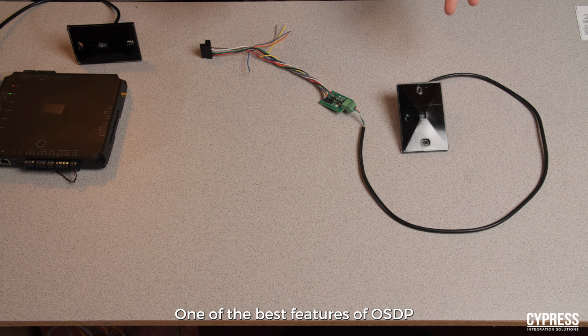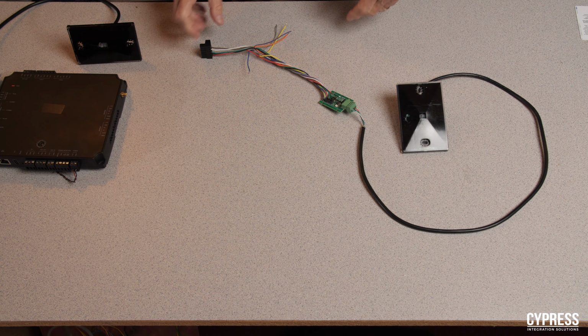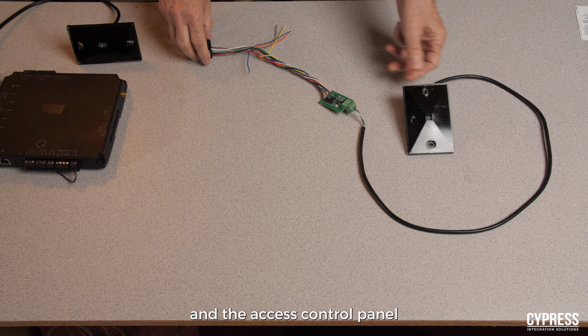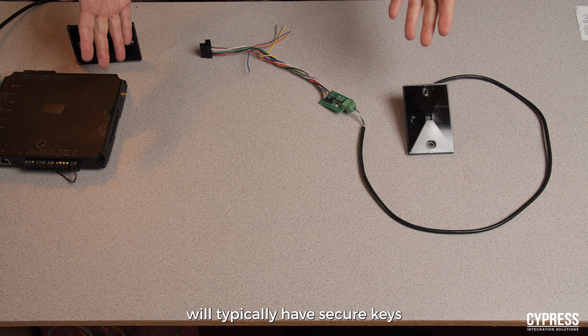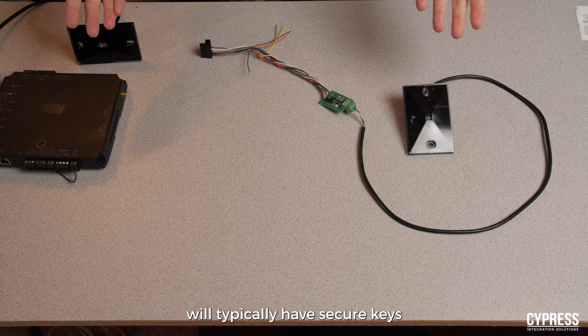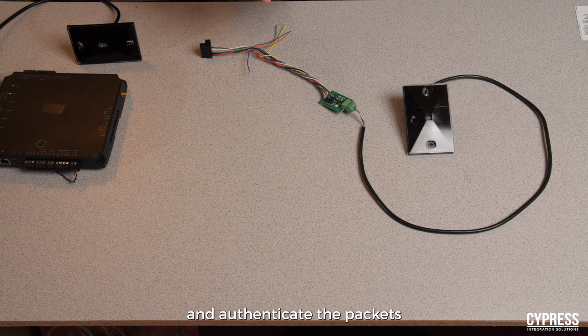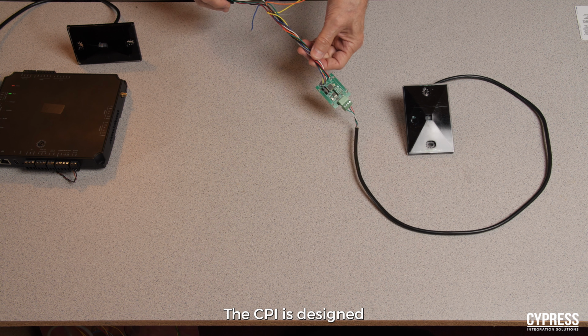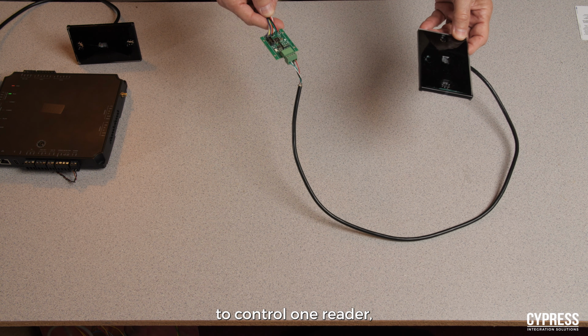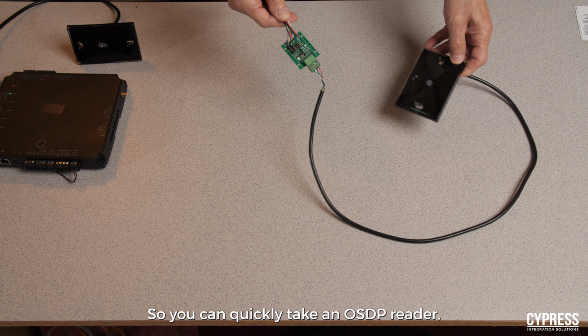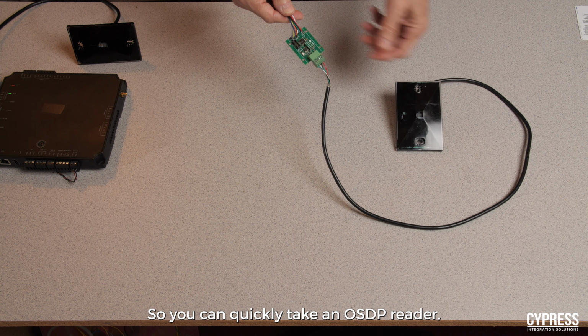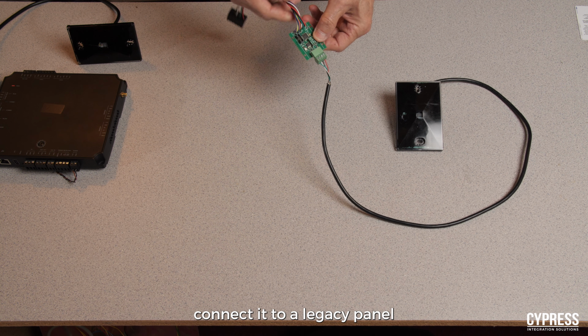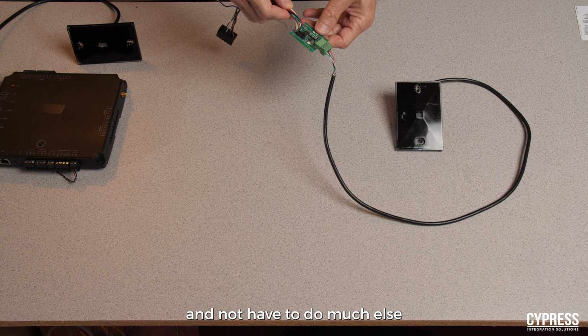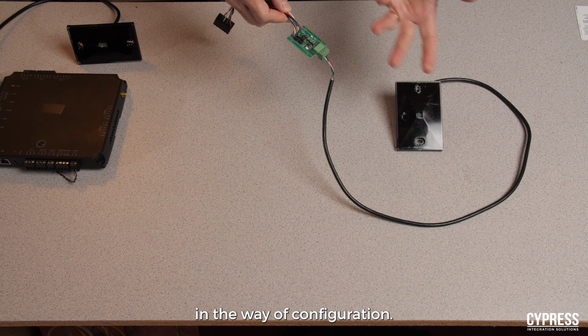One of the best features of OSDP is adding the secure channel protocol, which means that the reader and the access control panel would typically have secure keys that would encrypt and authenticate the packets going over the twisted pair. The CPI is designed to control one reader, so it's meant as a retrofit. So you can quickly take an OSDP reader, connect it to a legacy panel, and not have to do much else in the way of configuration.